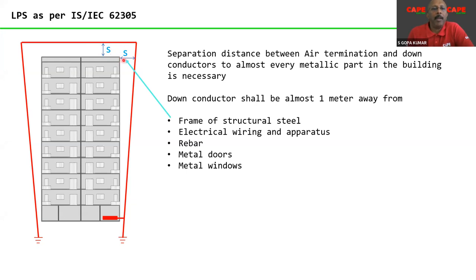and keep the air terminal and the down conductor physically away from the building. Away from what? Away from the frame of the structural steel, away from electrical wiring and apparatus, away from rebar, away from metal doors, away from continuously connected metal doors and windows. So basically, in order to avoid flashover, say for example, lightning is hitting this corner of the building, due to the surge impedance of the down conductor there can be a flashover from the air termination to the building. There are several flashovers at several locations of the building. In order to avoid flashover, technically, we keep the air termination and the down conductor physically away from the building at a separation distance. So it's very easy to understand.